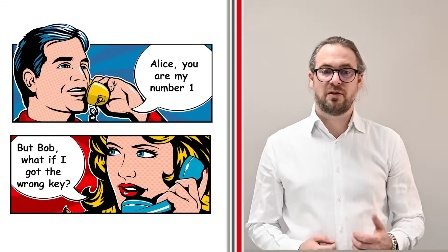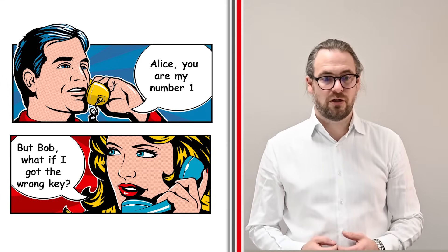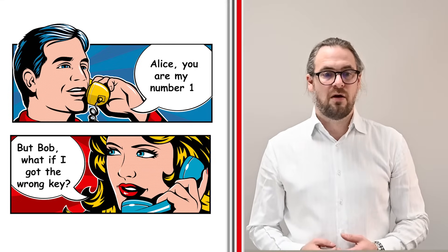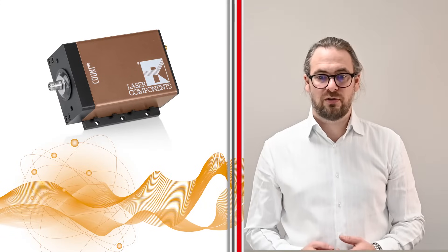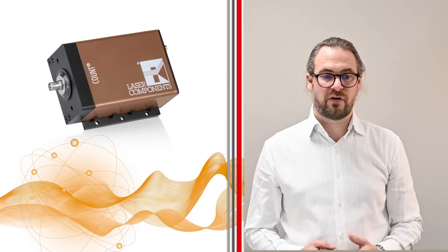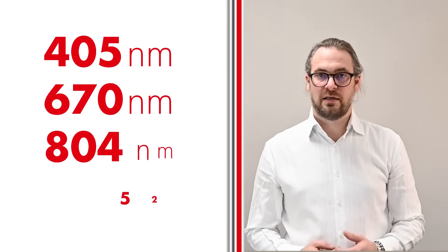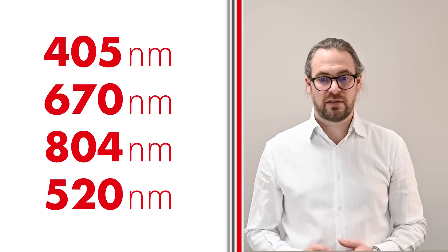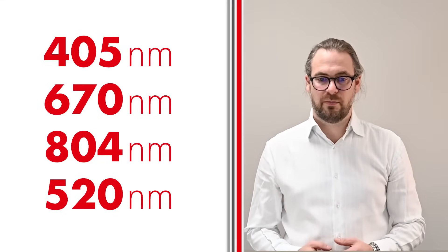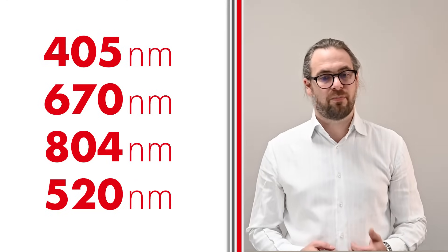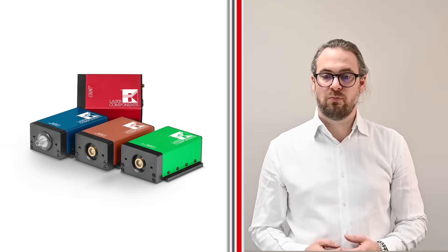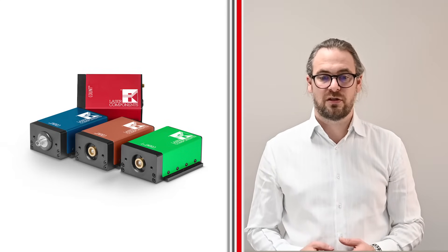To respond to the increasing demand of components used in quantum technology applications, we completely revised our concept for the measurement of single photon counting modules. Our new approach allows several fiber-coupled and free beam modules to be measured and characterized simultaneously. In addition to 405 nm, 670 nm, and 804 nm, it is now possible to measure even at 520 nm. The beam paths are adjusted automatically and the process flow from production to measurement has been optimized. The weak-link burn-in capacity for COUNT modules has been increased from 20 test stations to 80.